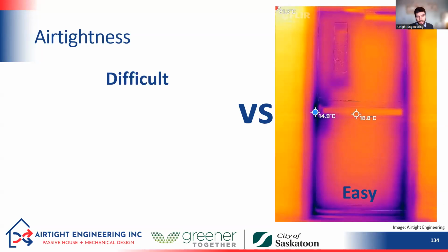But if we're, say, doing more of a deep air sealing job and we are sealing up any gaps around penetrations in the attic, we're adding air sealing to the basement, we're replacing windows with more airtight versions, and we're doing a lot of work to the envelope, we'll want to make sure that we add ventilation. So an HRV or an ERV, that heat or energy recovery ventilator, so that we are able to provide good ventilation air to the occupants still.